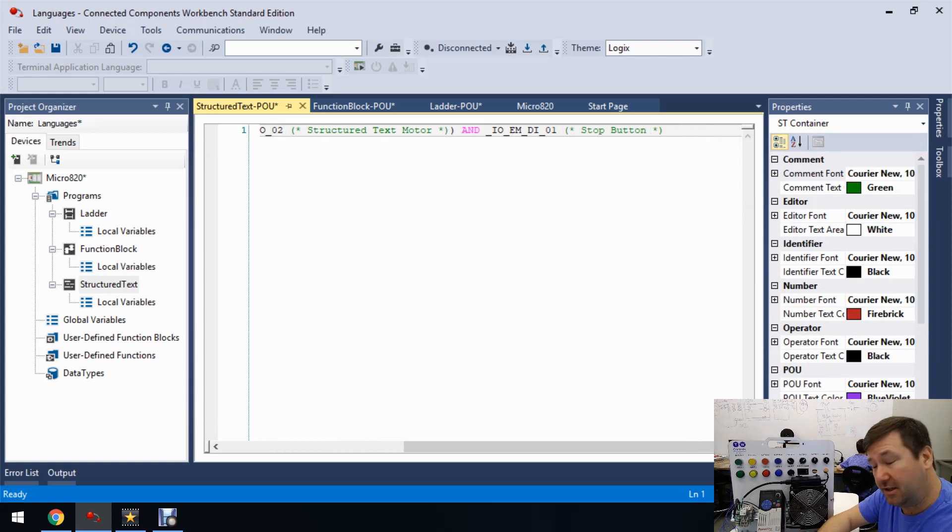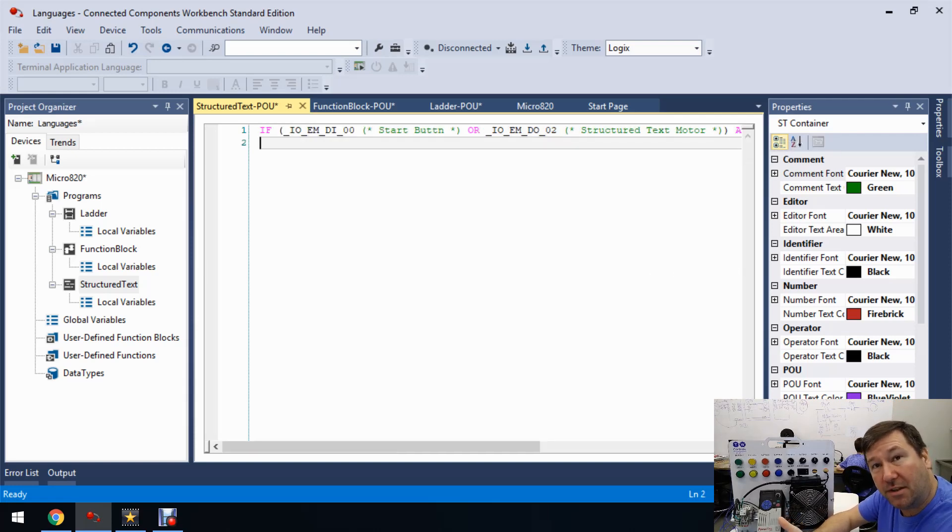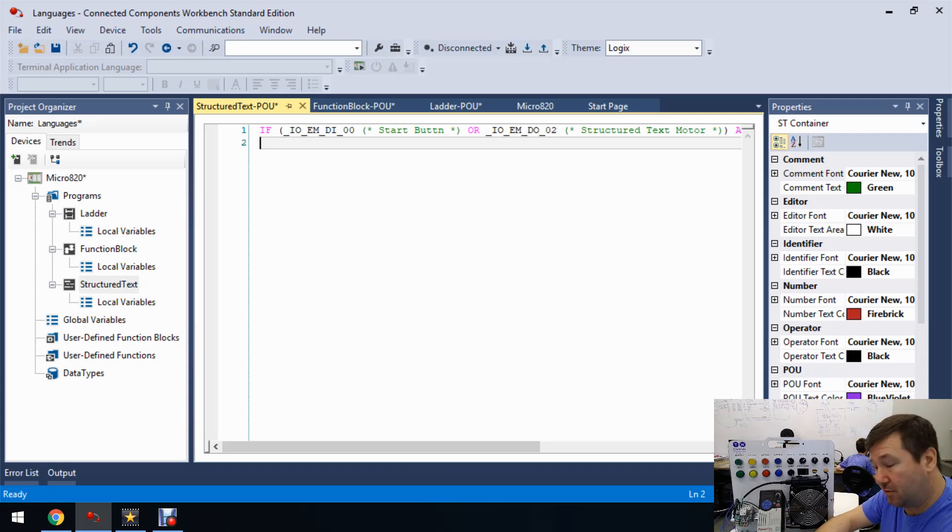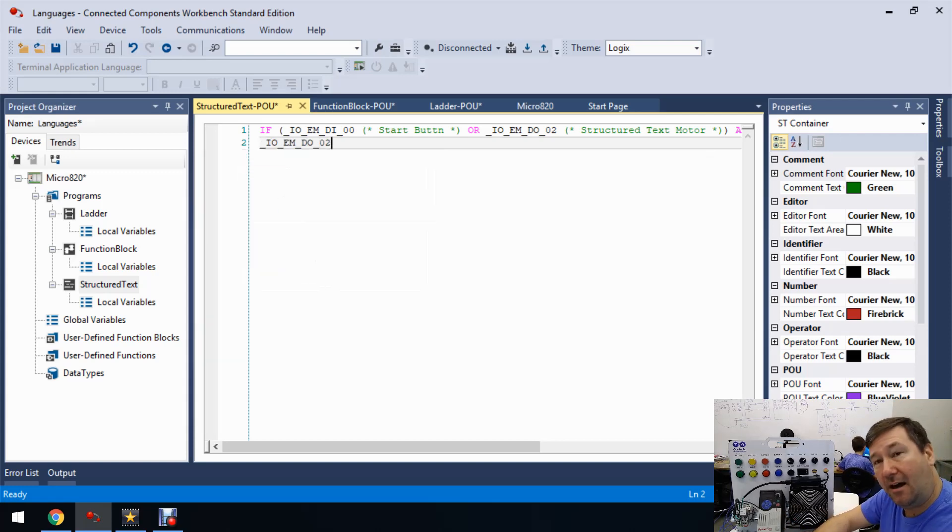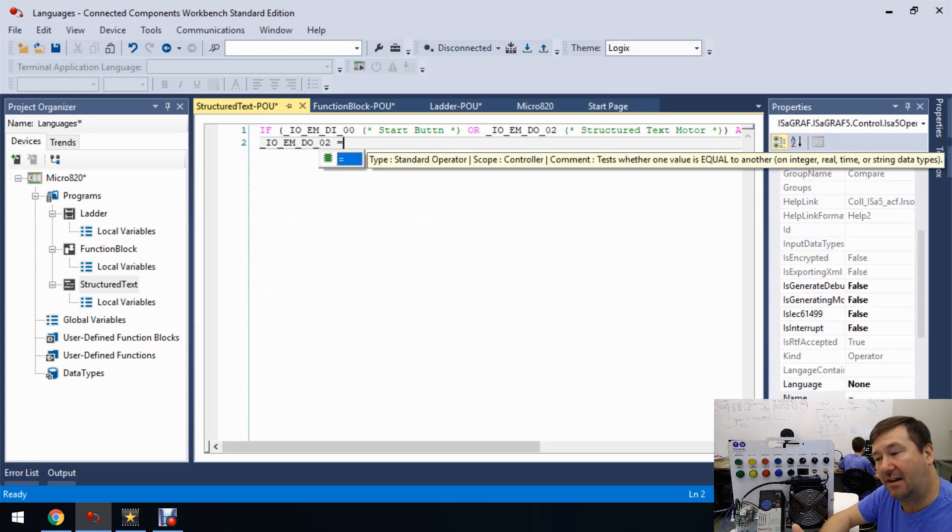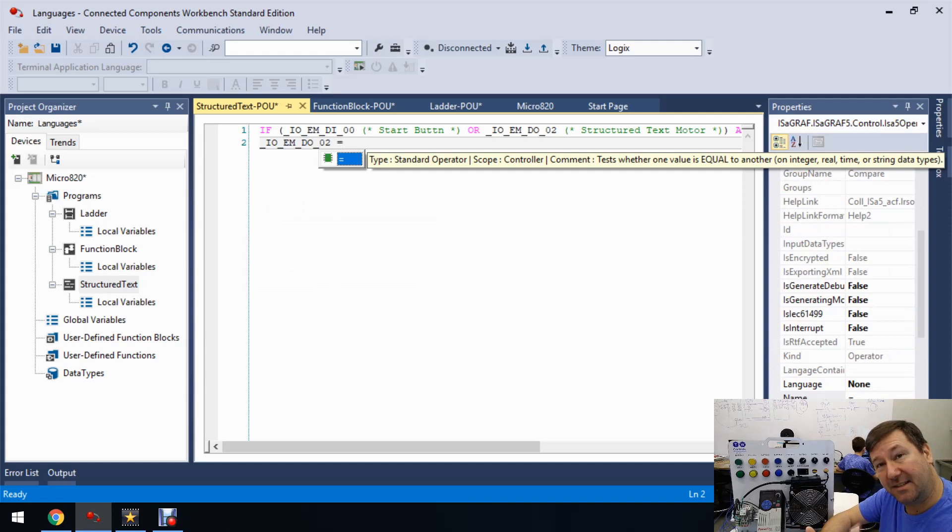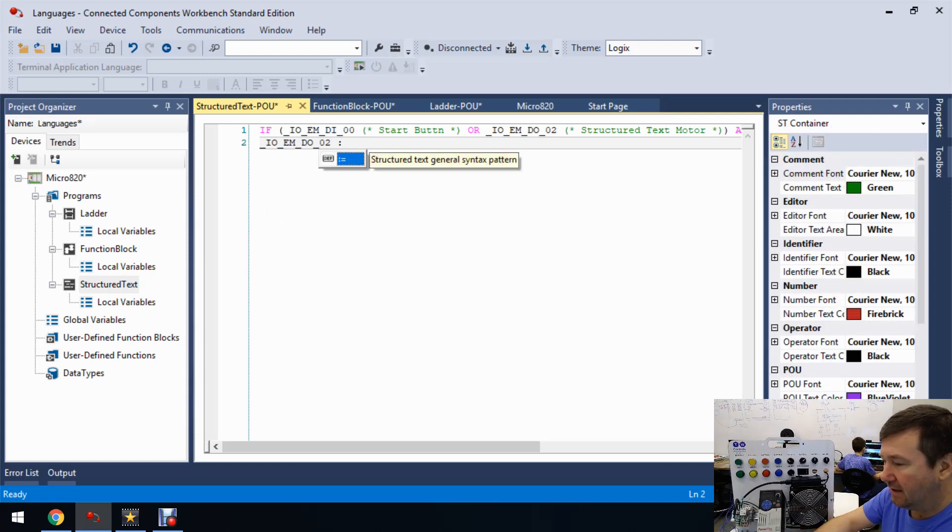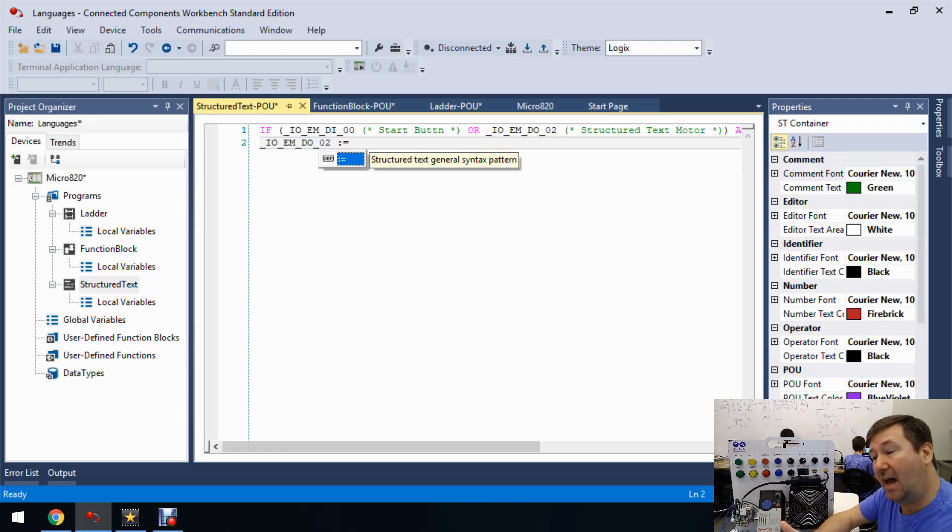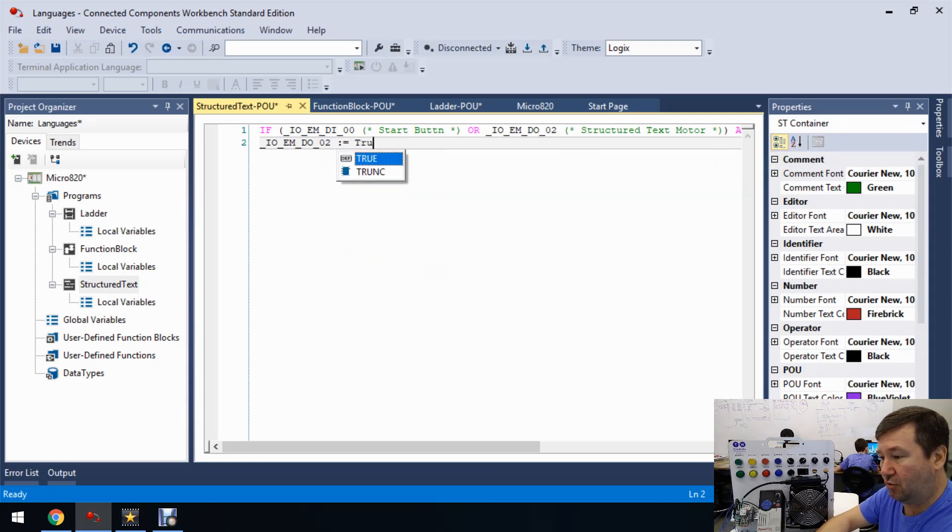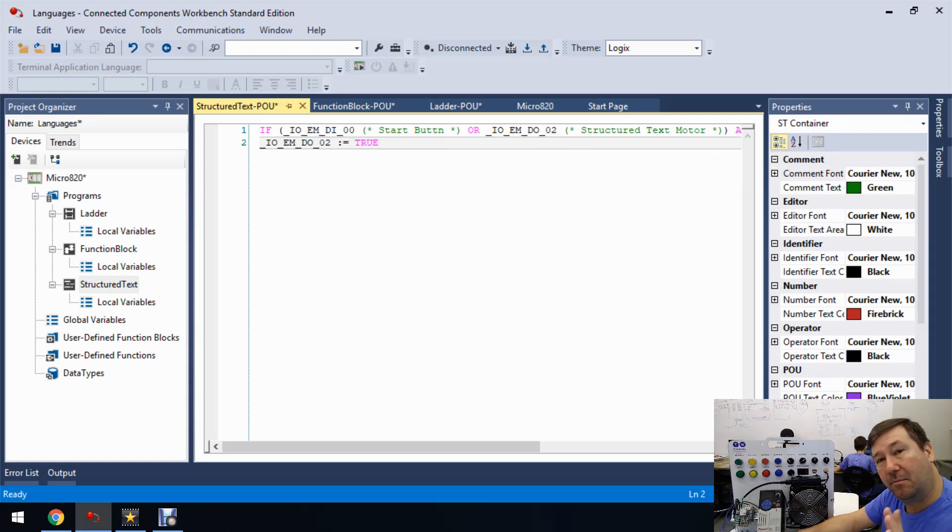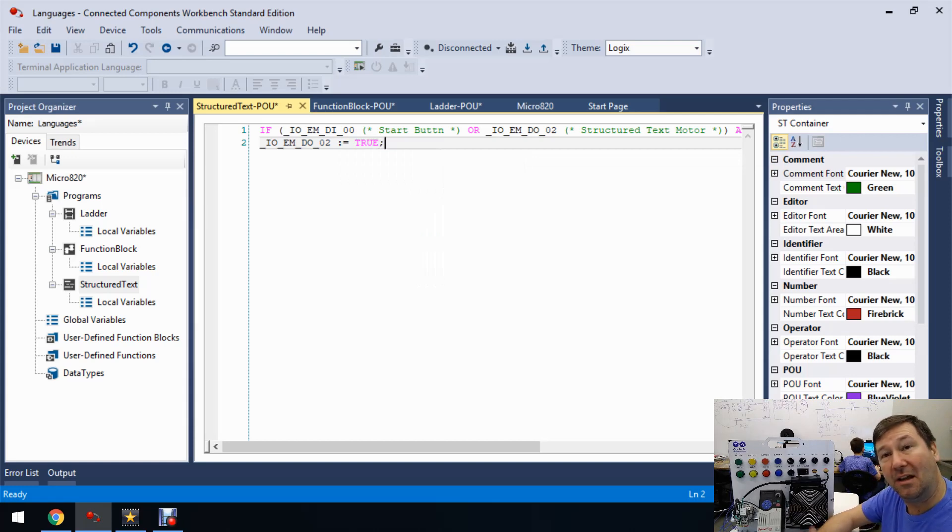And then once you're done with your conditions for your IF statement type THEN and then type what you want it to do if it's true. So if it's true, we want that structured text output to be true. Now you can't just do an equal sign on this because the equals is a compare. We need to do a colon equals and that's going to mean go write this value to that. So we want it to be true.